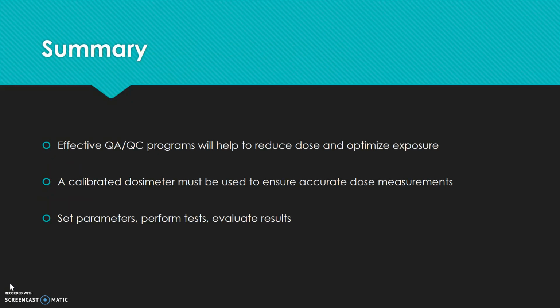In summary, effective QA/QC programs will help to reduce dose and to optimize exposure. A calibrated dosimeter must be used to ensure accurate dose measurements and to set parameters to perform tests and evaluate results.